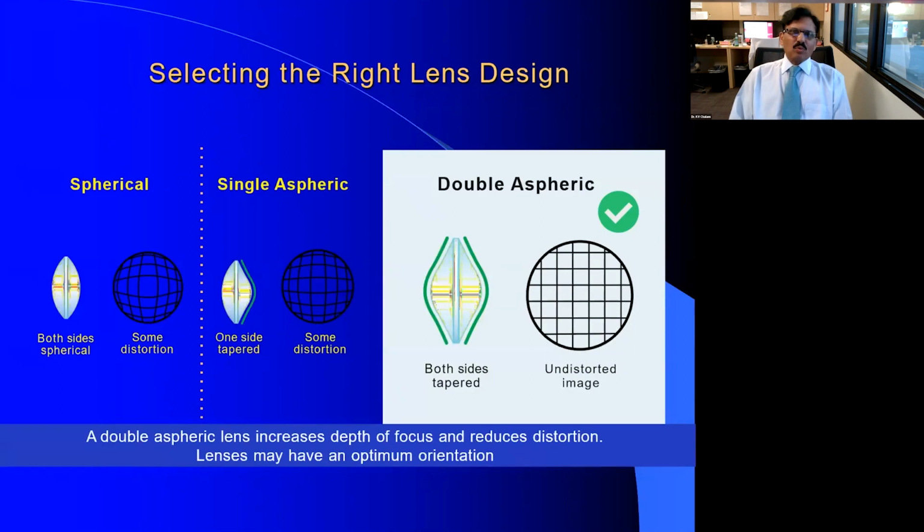And the second thing is what kind of lens design we want. The simple optics is that we basically use biconvex lenses. There is one other important manufacturing part that we need to bring attention to, which is called asphericity. A regular biconvex lens, as you go away from the central point, tends to have both chromatic and spherical distortion, like a barrel shape right here.